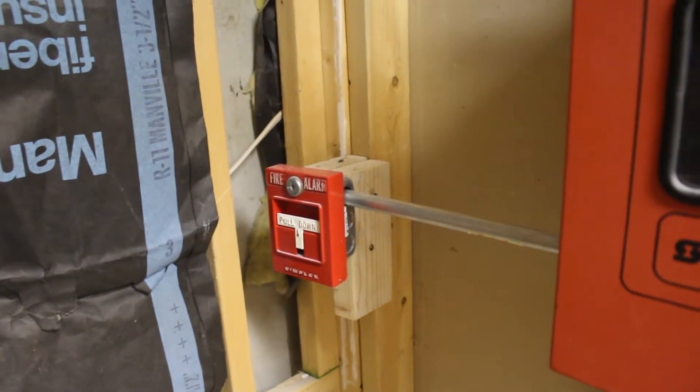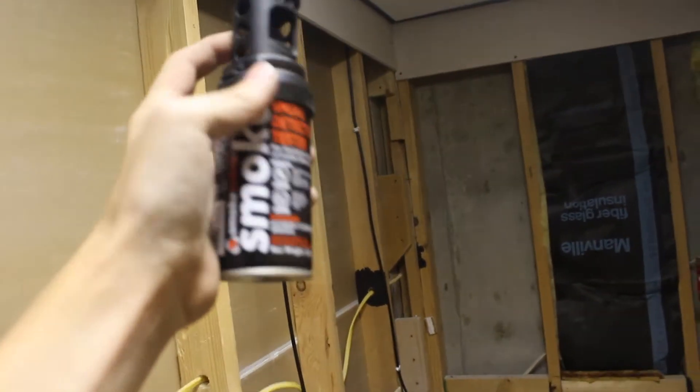I'm going to start to move this pull — actually don't know where the keys are currently, so we're not going to pull it today. But we do have the smoke saver, so we're going to go ahead and test the detector.